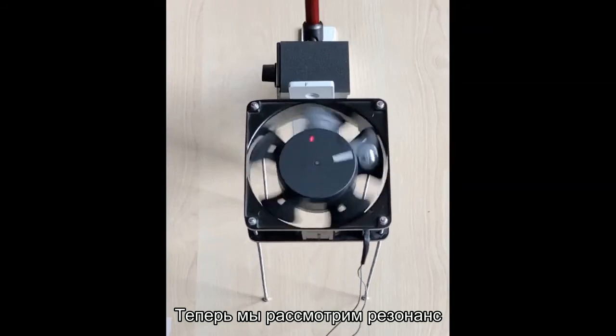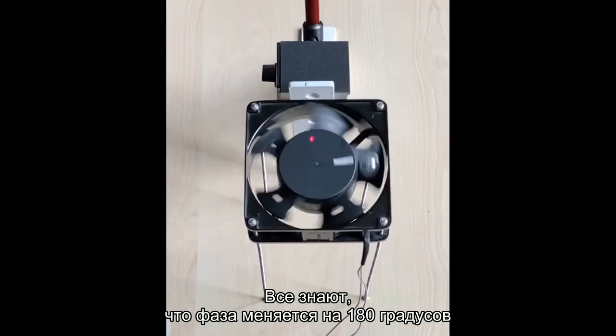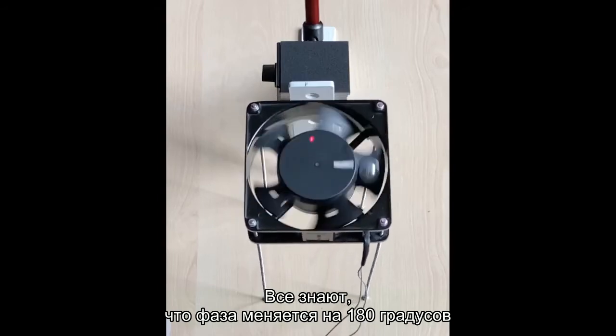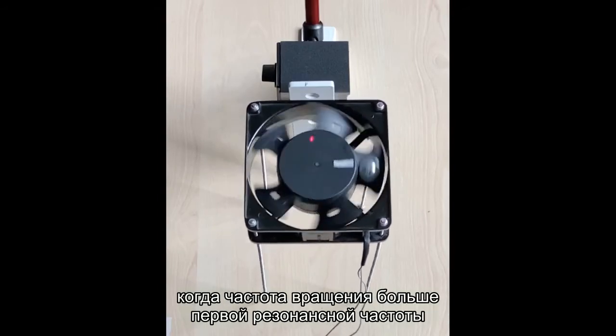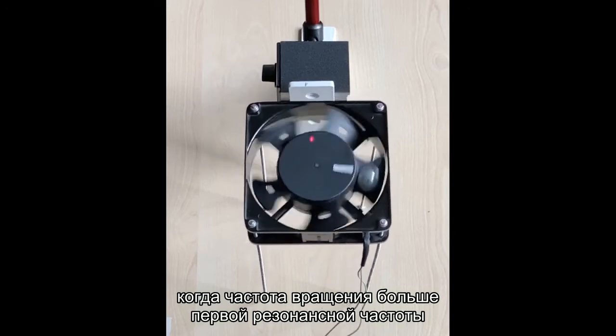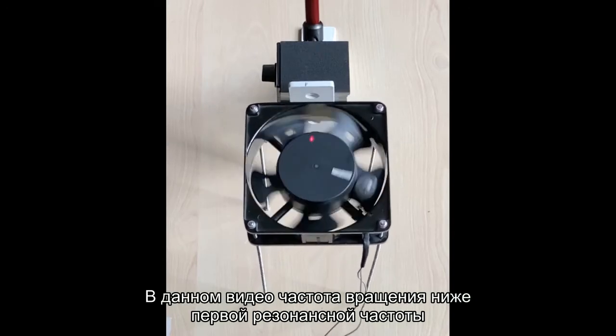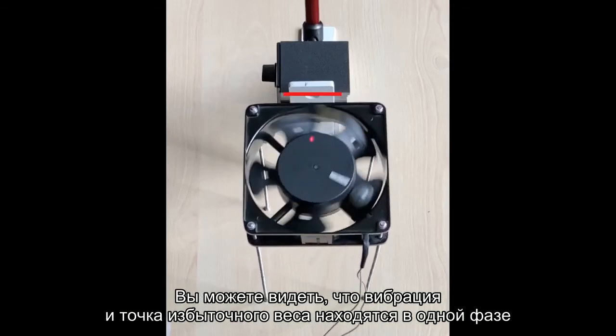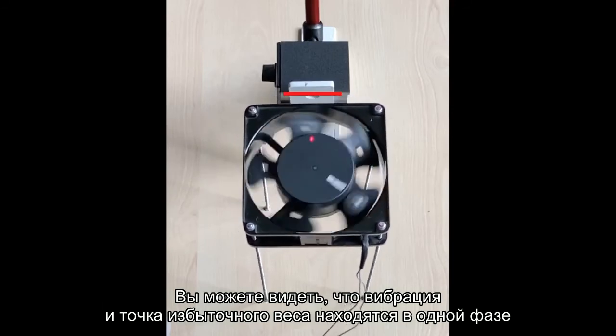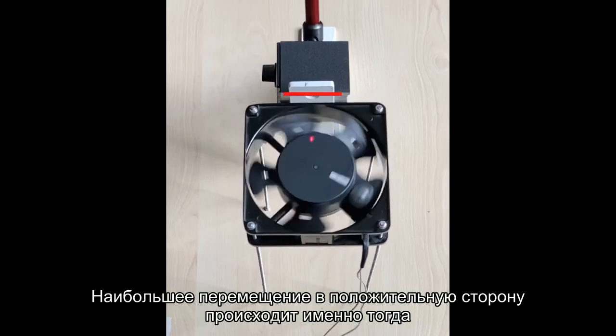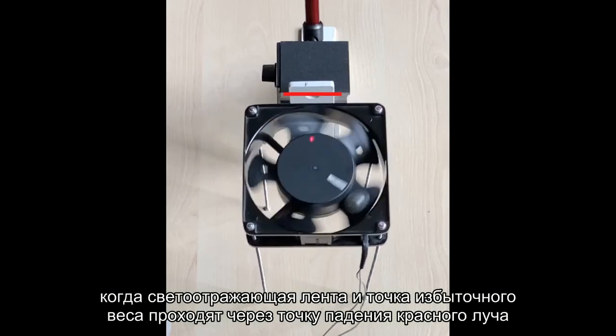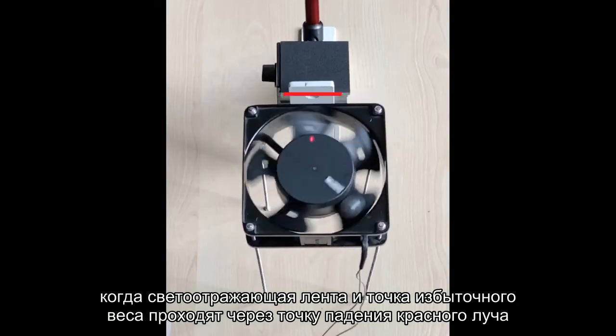Now we will look at the resonance. Everybody knows that the phase changes by 180 degrees when the speed is higher than the first resonance frequency. In this movie, the speed is lower than first resonance. You can see that the vibration and the heavy spot are in phase. The highest positive displacement occurs just when the reflective tape and heavy spot are going through the red ray point.